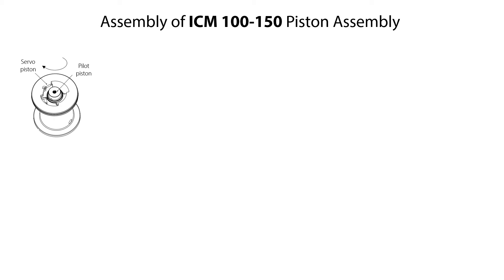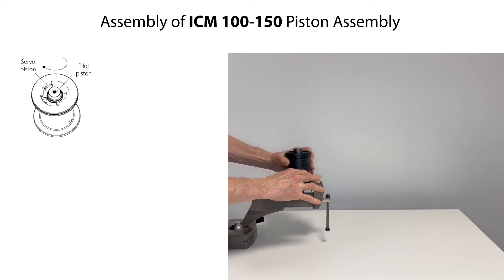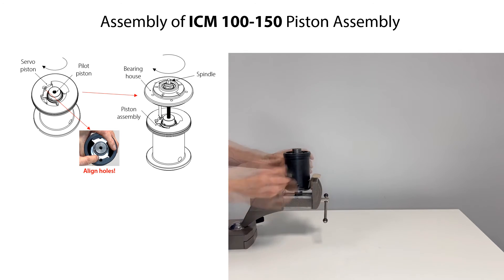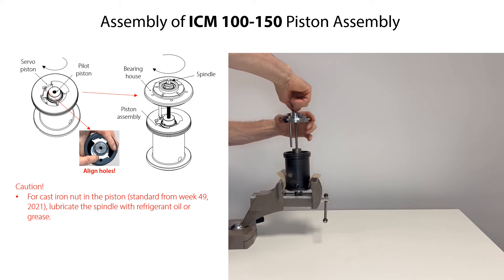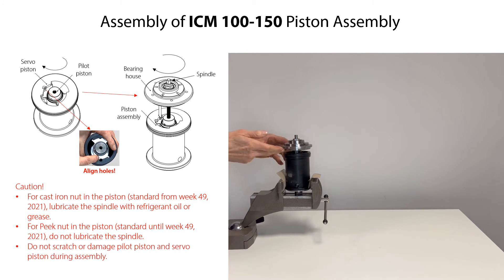To assemble the piston assembly, mount the spring inside the servo piston. Push the pilot piston into the servo piston by rotating it clockwise with a suitable tool until it is fully fixed. Ensure that the holes in the piston are aligned so that the bearing house can be located correctly. Mount the spindle and bearing house into the piston assembly and rotate them clockwise until fixed. Please note that for a piston with cast iron nut, which is standard from week 49, 2021, lubricate the spindle with refrigerant oil or grease before mounting it. For a piston with PEEK nut, which was standard until week 49, 2021, do not lubricate the spindle. Be careful not to scratch or damage the pilot piston and servo piston during assembly.